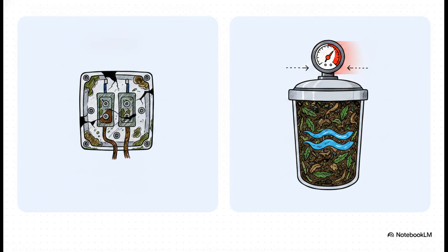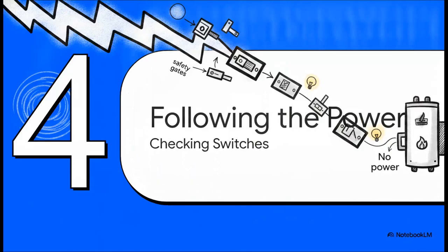But a water flow problem? That means your dirty pool filter, clogged skimmer, or maybe closed valves are restricting the water. In this case, the switch isn't broken at all. It is heroically keeping the heater off to save it from destroying itself from dry heat. That is exactly why you must always check your filter pressure gauge first before doing anything else. Let's head into Section 4, following the power and checking safety switches.